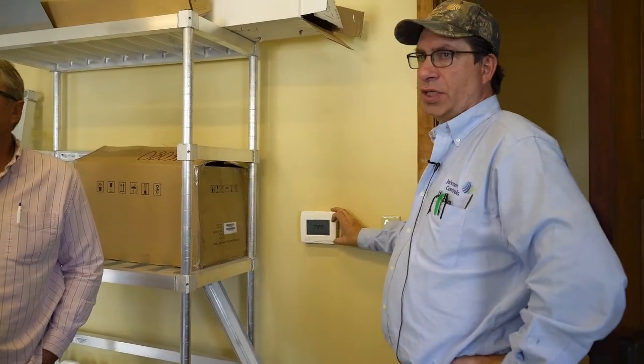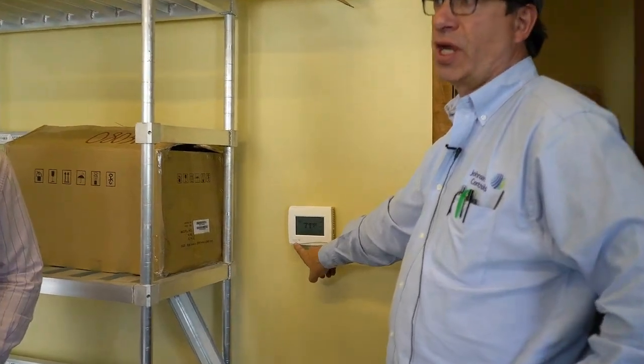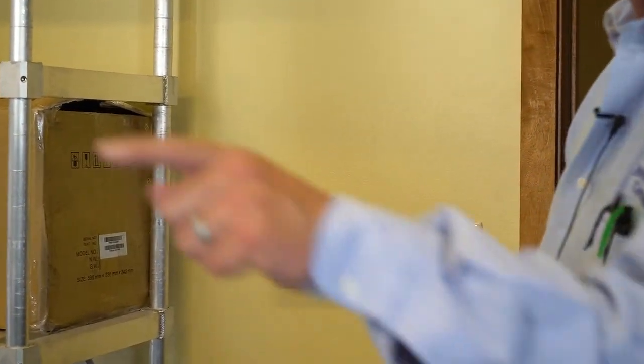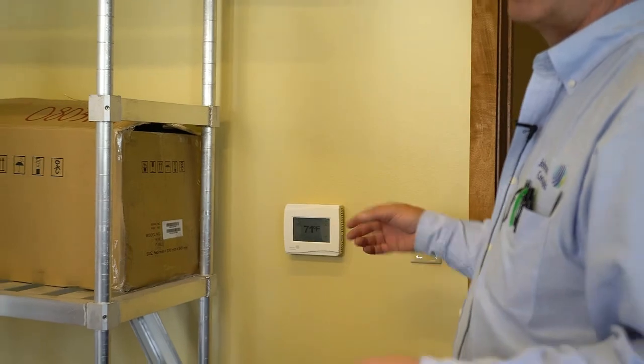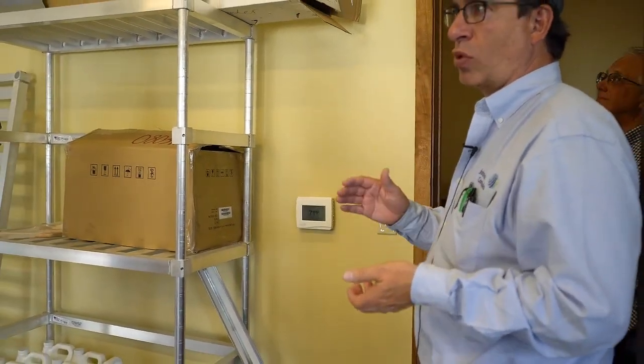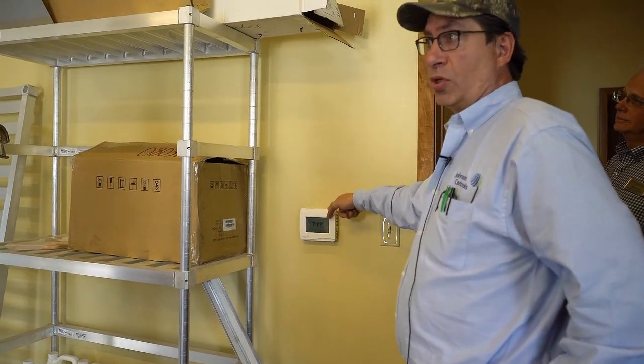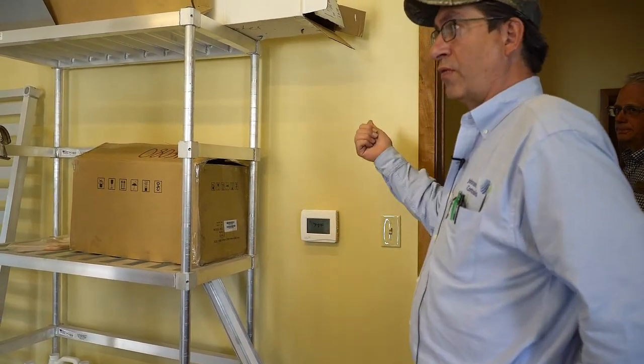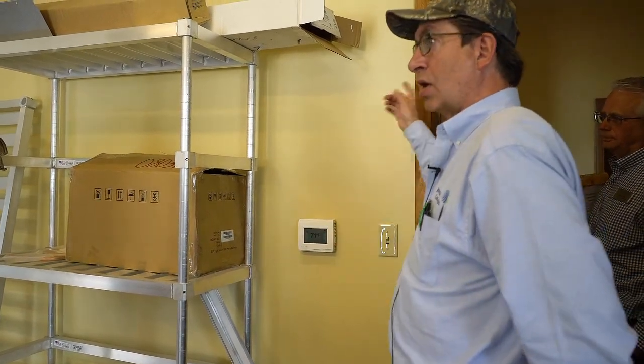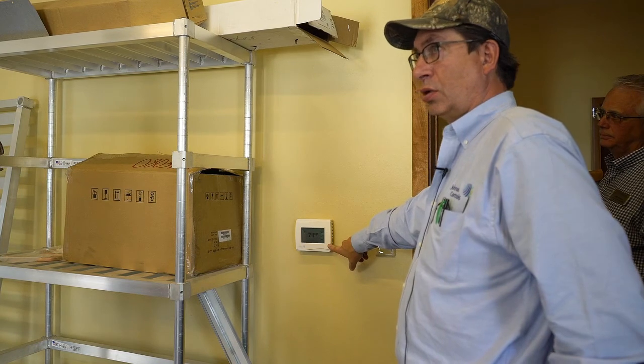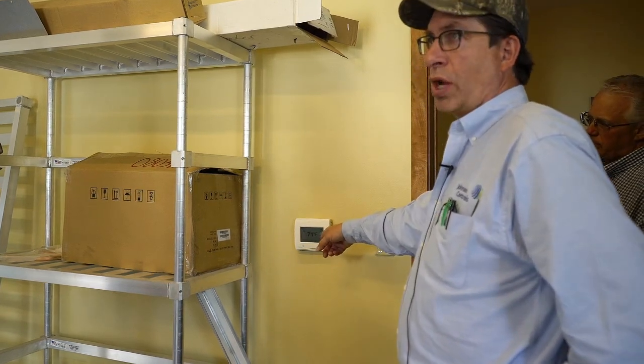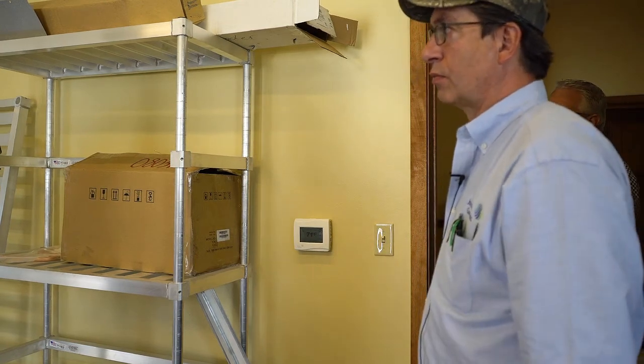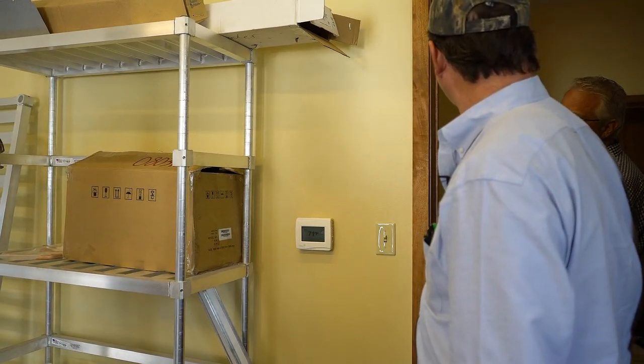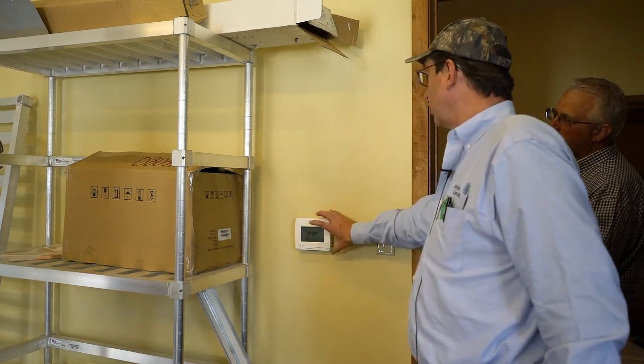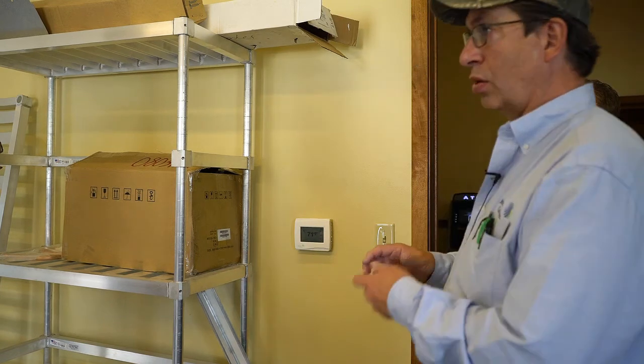All right, so here we have a typical TEC Johnson Controls thermostat. On this project, these thermostats are controlling the fin tube on the wall. These just control those valves on there. As the temperature drops in the room, it'll start modulating that heating valve to maintain set point. These have our trunk coming to them so that we can actually read these points and pull them onto the front end. So you have a trunk wire coming in and coming out of here. You've got 24-volt power coming in here to power up the stat, and then you have a 3-wire going over to the control valve to modulate it. And if you have to change the stat out, what's the process? You'd have to pull the cover off, pull the back plate off, unwire the wires, wire them to the new one, and reinstall.